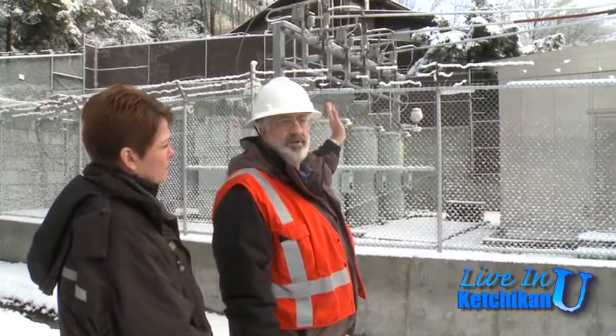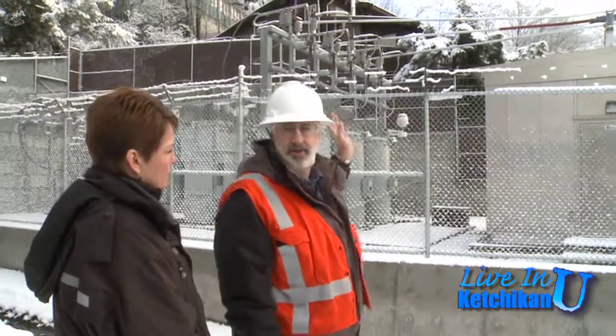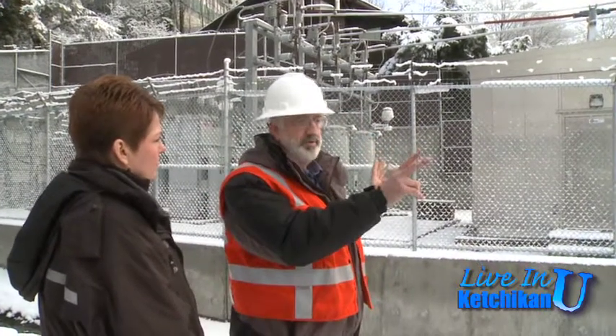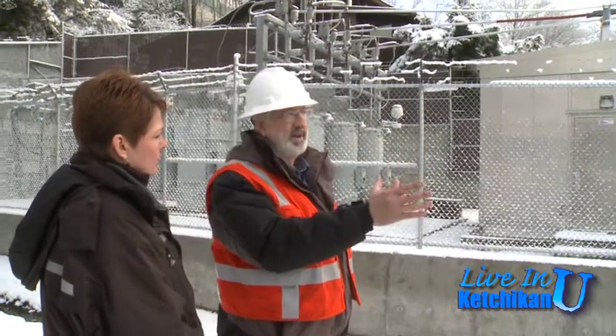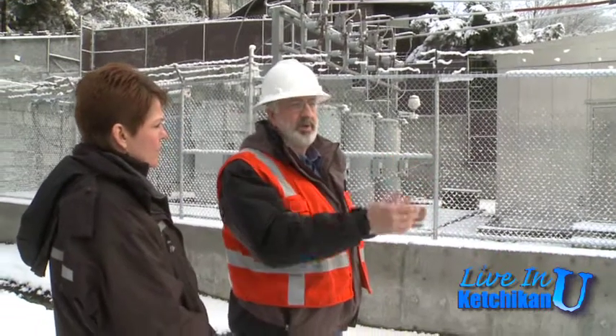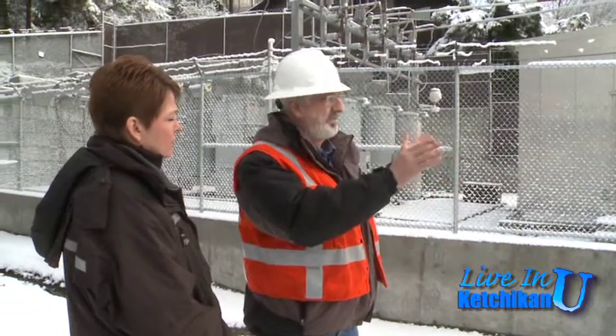The Jackson feeder picks up pretty much the 4 schools up the hill and some residential area. So those are the two feeders, and they happen to be almost identically sized. On a typical winter day, they've got about 3 megs of load on each of them.